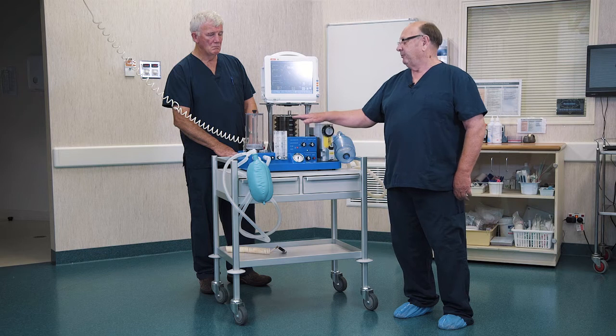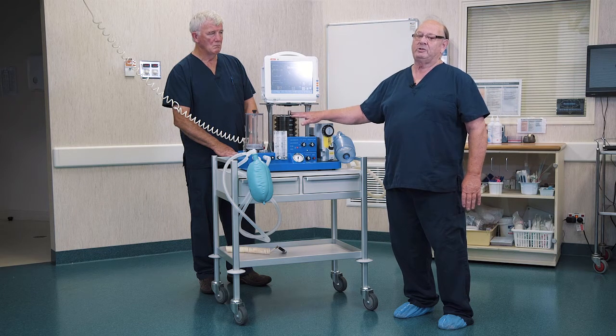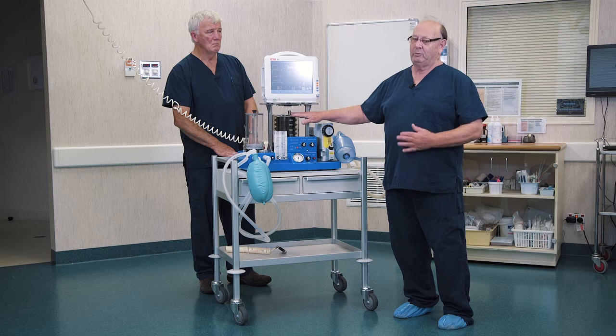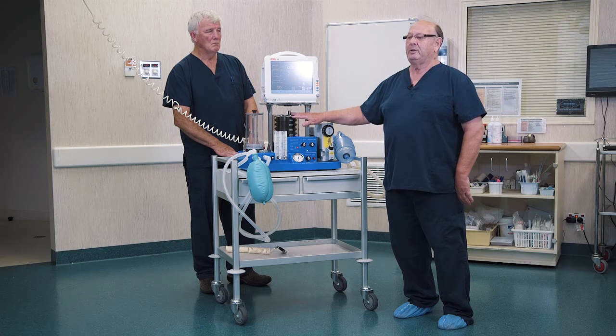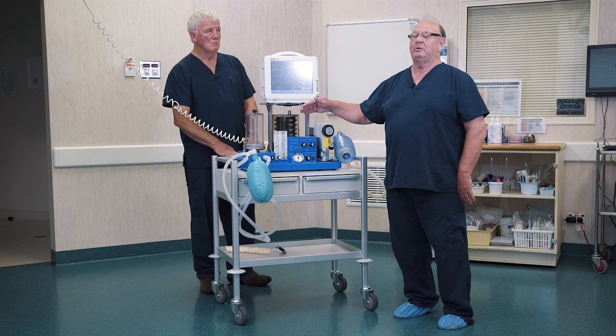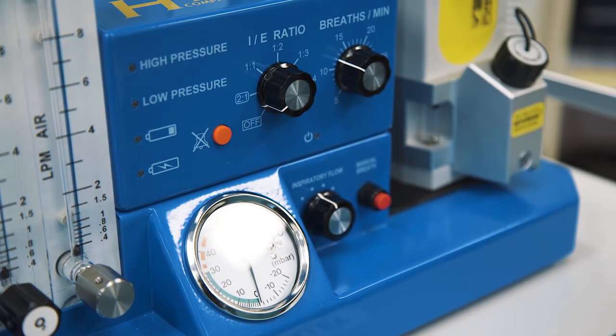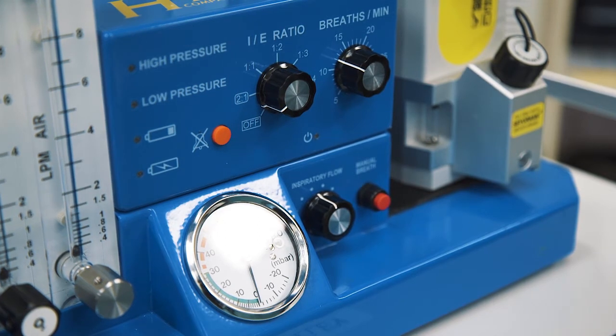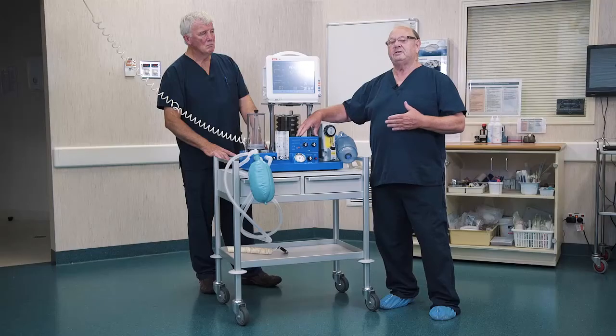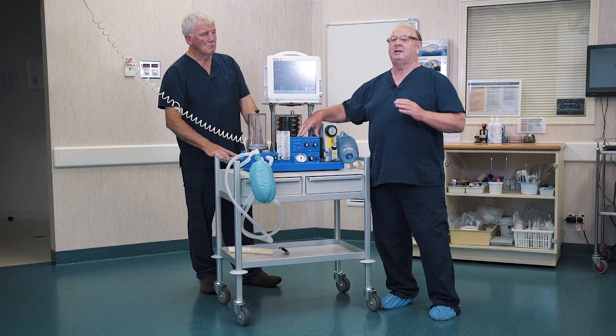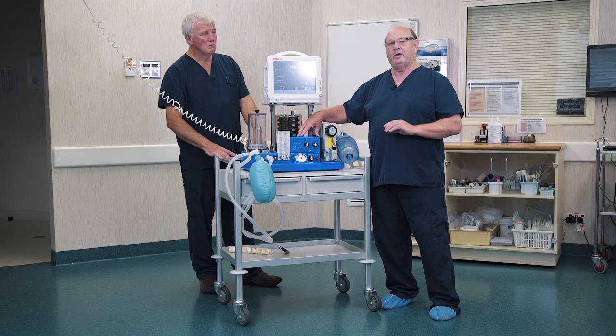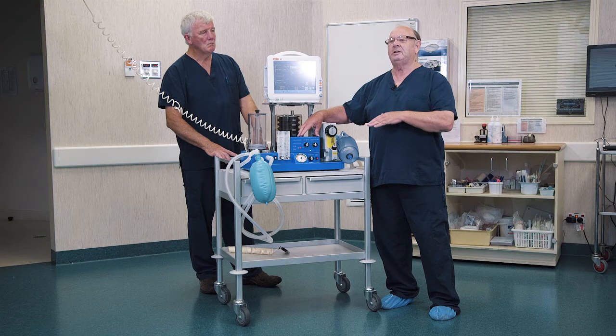If for some reason there's a leak or you run out of oxygen, although running out of oxygen would also give you a pressure alarm, there's a negative pressure alarm which will alarm if the patient has no oxygen. And also the smart thing about this ventilator is it runs on 60 psi. When you connect the gas, it senses the pressure and it sets the alarm value at about 60% of that pressure. If you're running off a concentrator at a reduced pressure of around 15 psi, it will automatically set the alarm pressure at about 10 psi. It does all this automatically.